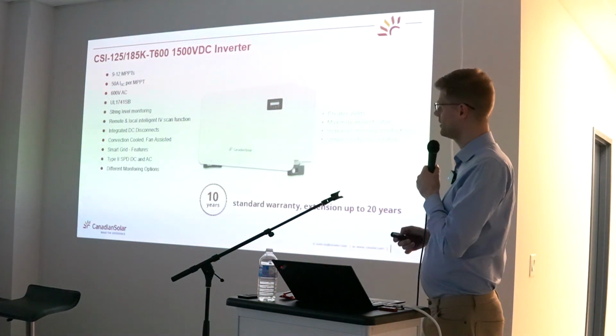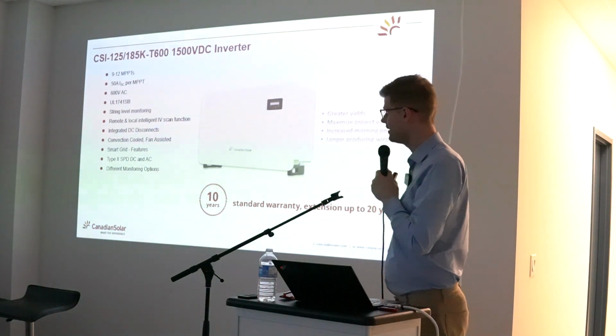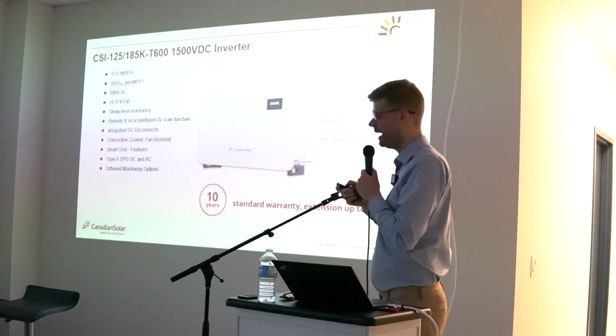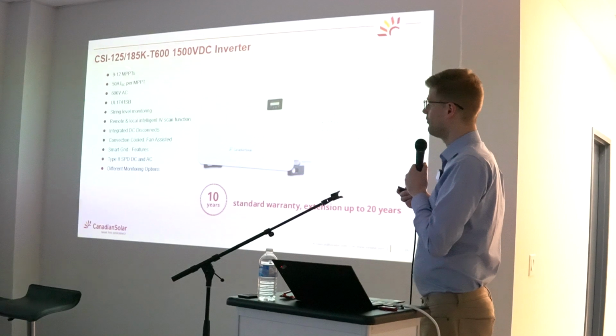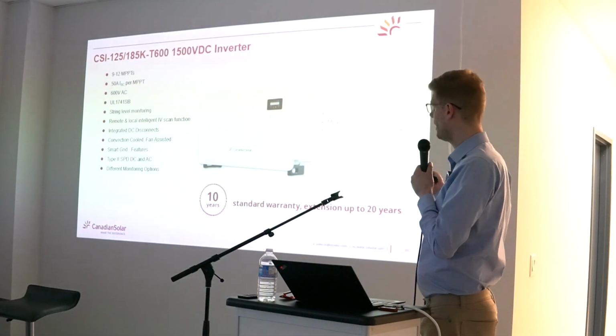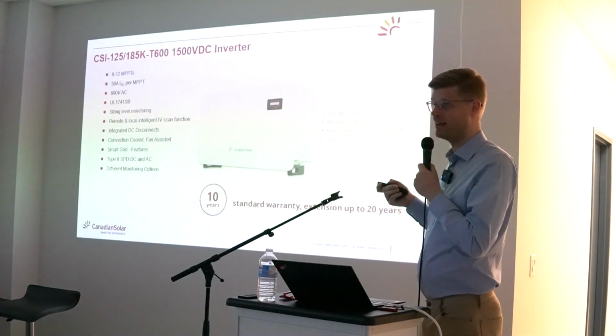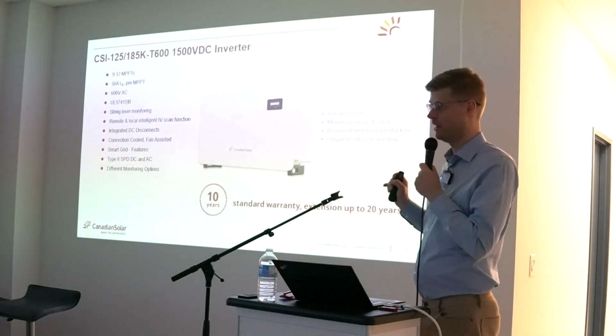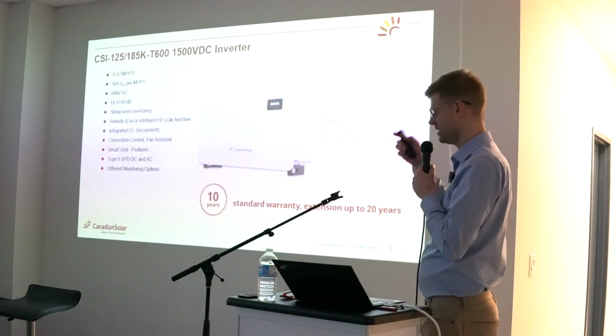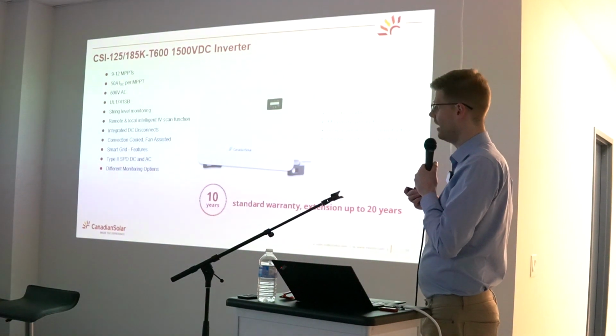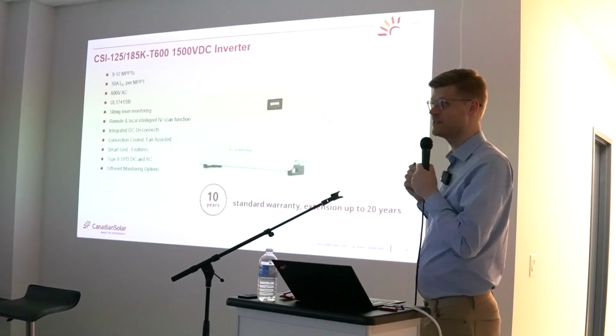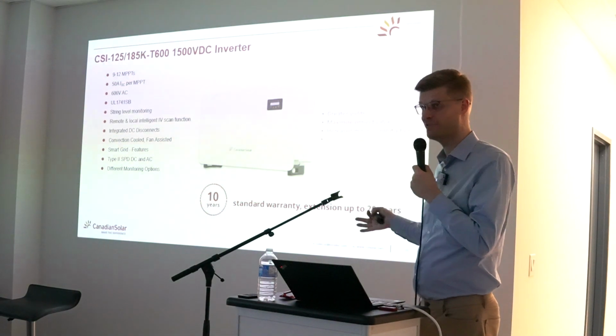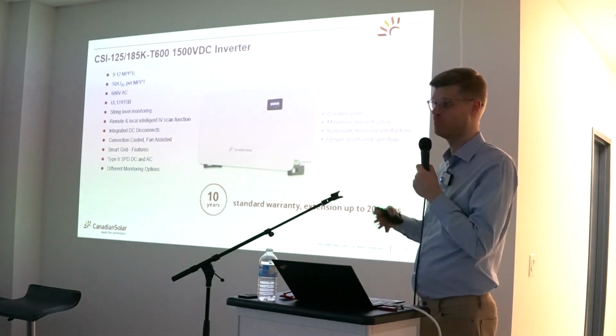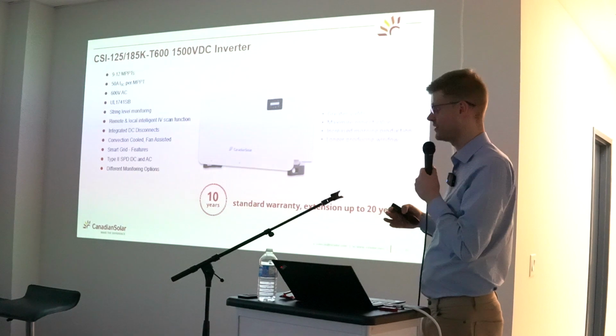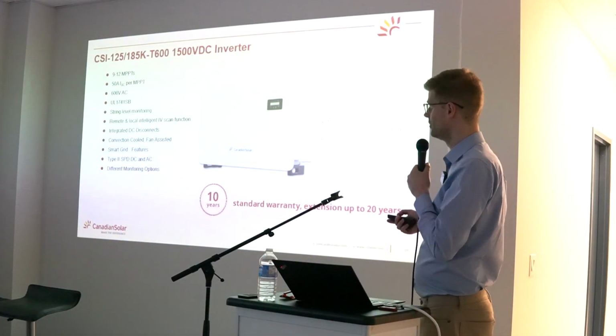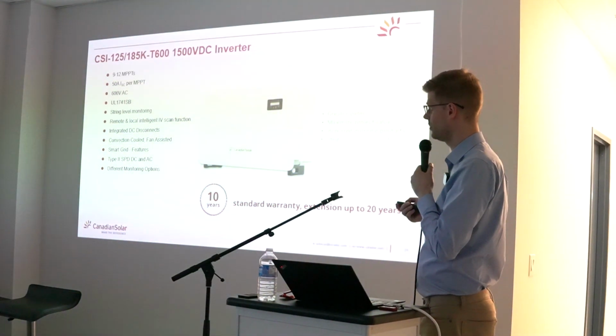A quick summary, just the biggest points why this is an extremely good fit. I mentioned most of those already. You have multiple MPP trackers, you have an extremely high power class. The 50 amp ISC current rating is really phenomenal in the industry. They're significantly higher than many other products on the market. You have a native 600 volt AC connection, which is amazing for the Canadian market for commercial because most of the connections are 600 volt as well, so you don't need a transformer to step down to 480 if you only use a 480 volt string inverter.